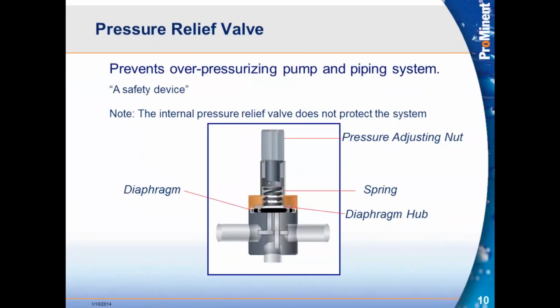The pressure relief valve is very similar. So as we mentioned, with the back pressure valve, we're establishing a minimum pressure that the pump is going to have to pump against. Now, if the system exceeds that, the pump is going to continue to pump because we're already opening the back pressure valve up to its maximum pressure. But now we want to establish a maximum pressure. So if we control those two things, if we control that pulsation, we're going to get nice, reliable, repeatable results, and we're going to get nice longevity out of the pump as well. We're not going to destroy the pump. It's going to last a long time. It'll help the diaphragm on the pump last that much longer as well.